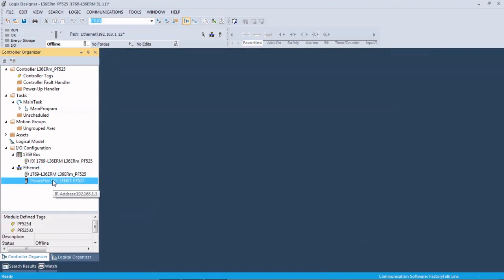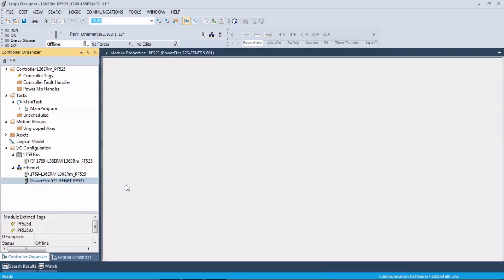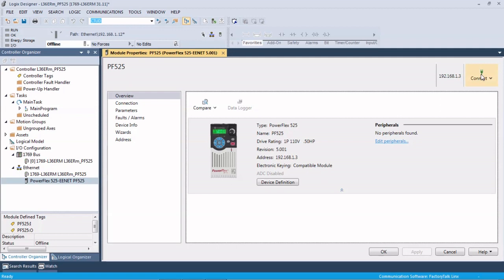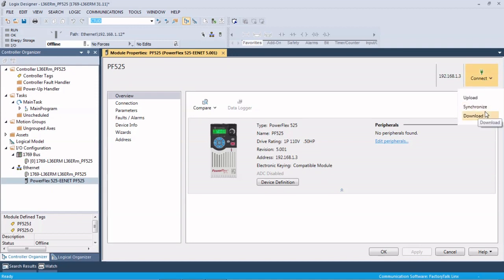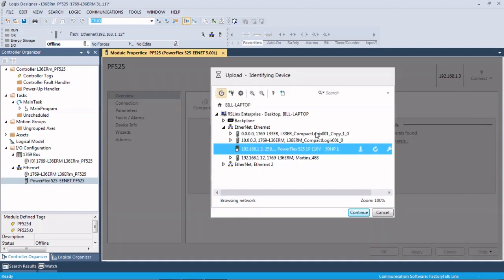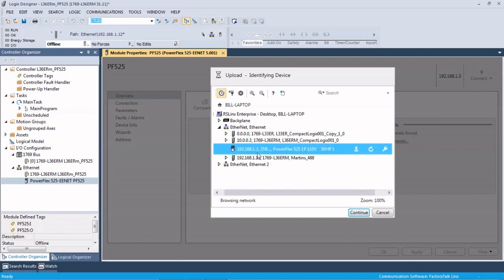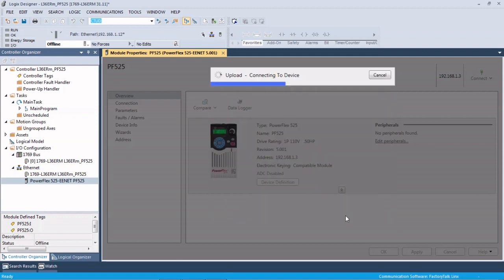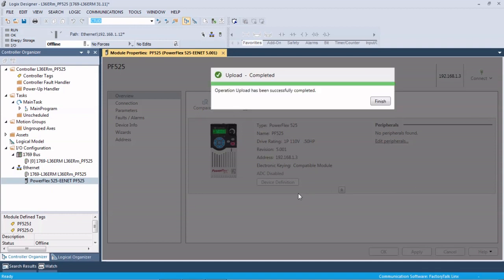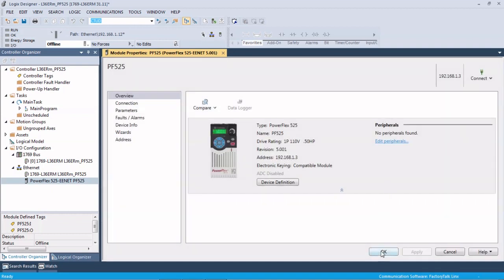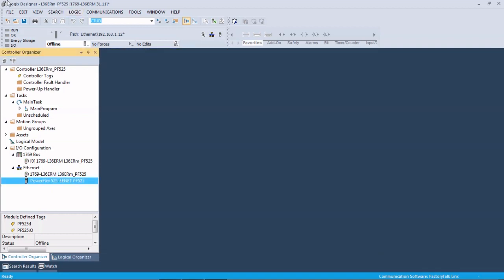Let's close this and we're going to open this back up. This connect button up here, what we're going to do is upload the parameters off the drive to match what we have in the program, and then that way we can go online without any issues. So we're going to upload from the drive. Here it is. Bring up our RSLinx. We know it's on our Ethernet port, and there it is at dot 3. We're going to upload, hit finish, and OK.